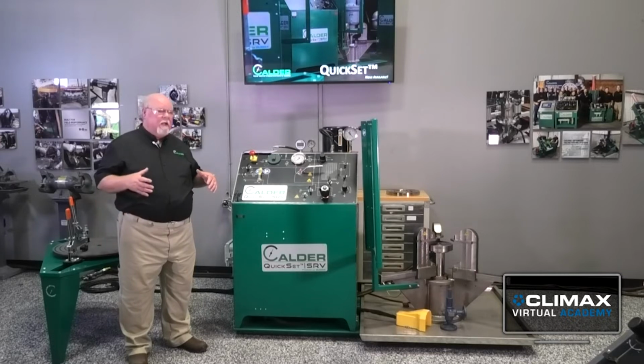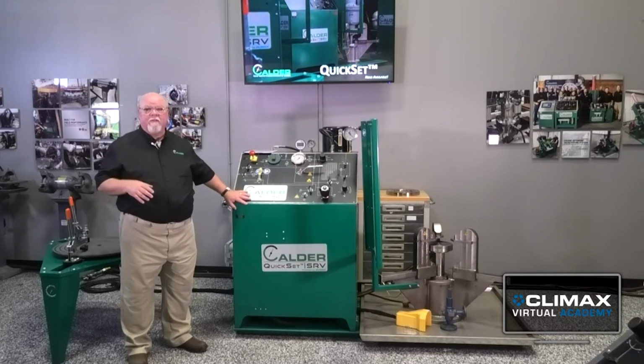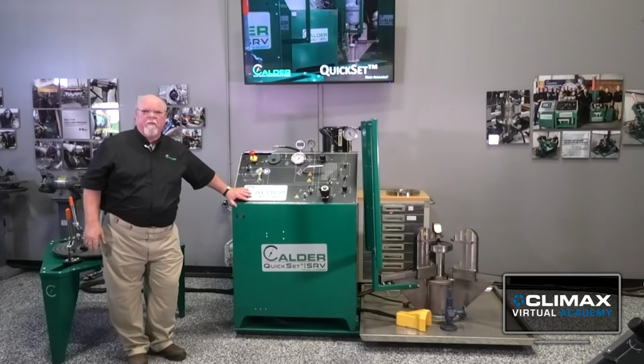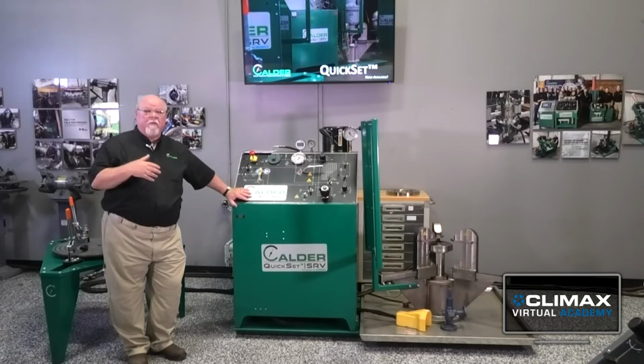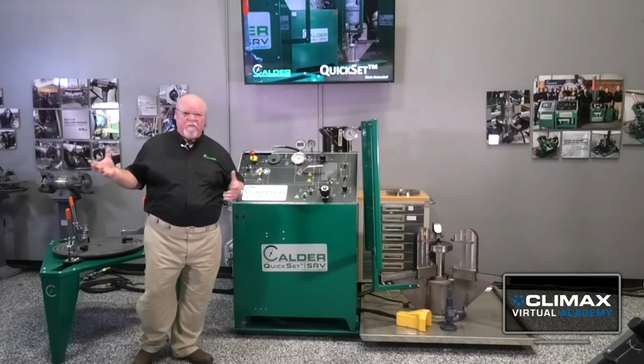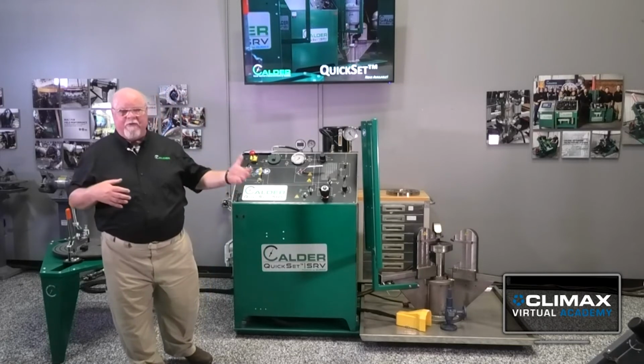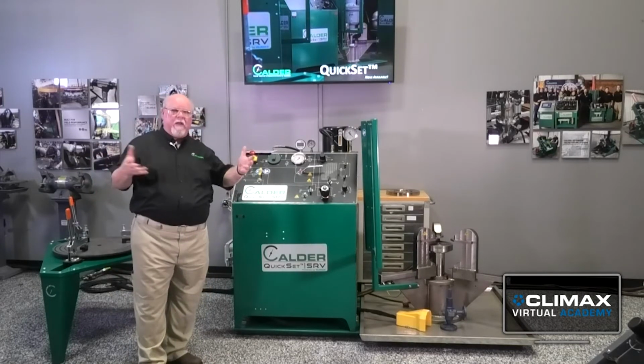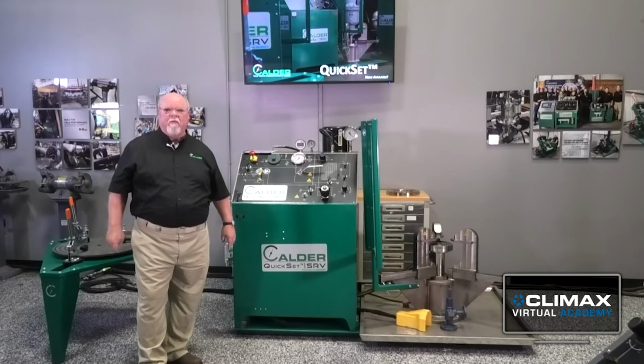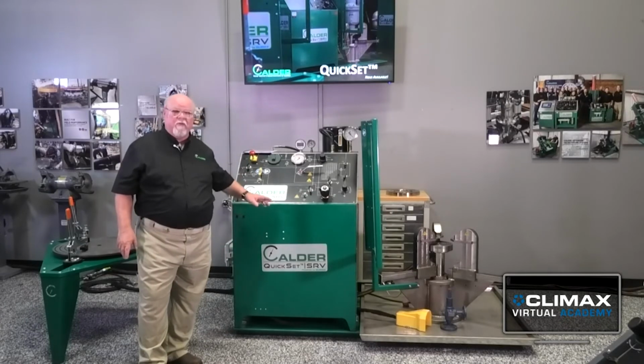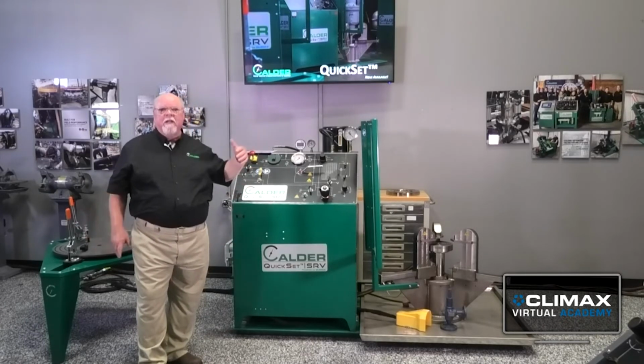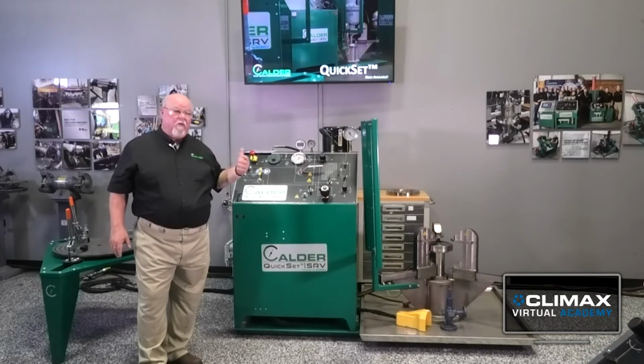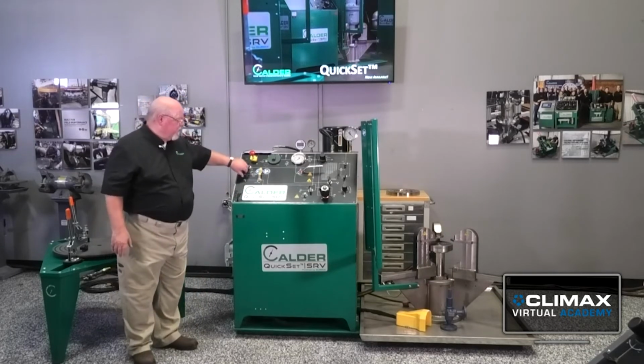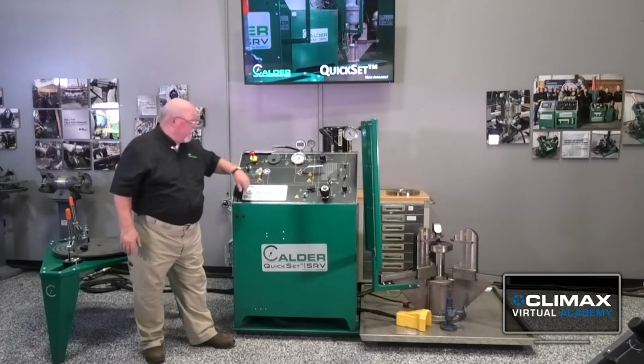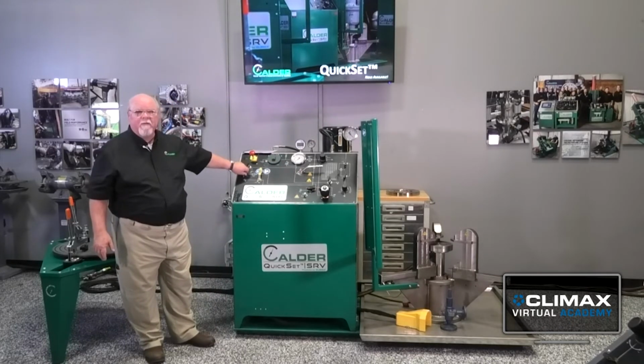As far as the air or the test gas that's needed to run this unit, we have a couple of options. We have a fitting on the back, so if you have nitrogen bottles, you can obviously regulate nitrogen down to the inlet, up to 6,000 psi, and test all day long that way as well. If you want to put this into a container and take it to the field, we have an internal booster pump, and to hear it run, this unit's set up for that.